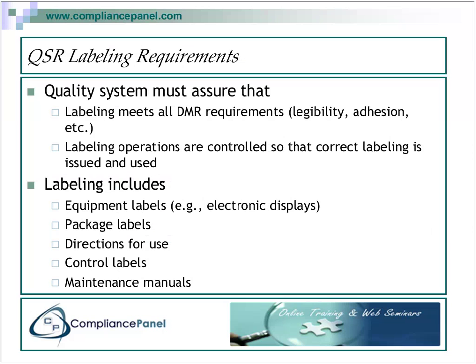Back to the QSR labeling. The quality system regulation put out by the FDA has certain labeling requirements, and your quality system has to assure that your labeling meets all of your device master record requirements: legibility, adhesion, can it stick, etc. Your labeling operations must be controlled so that the correct labeling is issued and used. Now remember that labeling includes equipment labels, package labels, directions for use, control labels, maintenance manuals, all sorts of these things. Your quality system must be sure that the correct labeling is issued and used, and you have to be able to verify that and prove that.